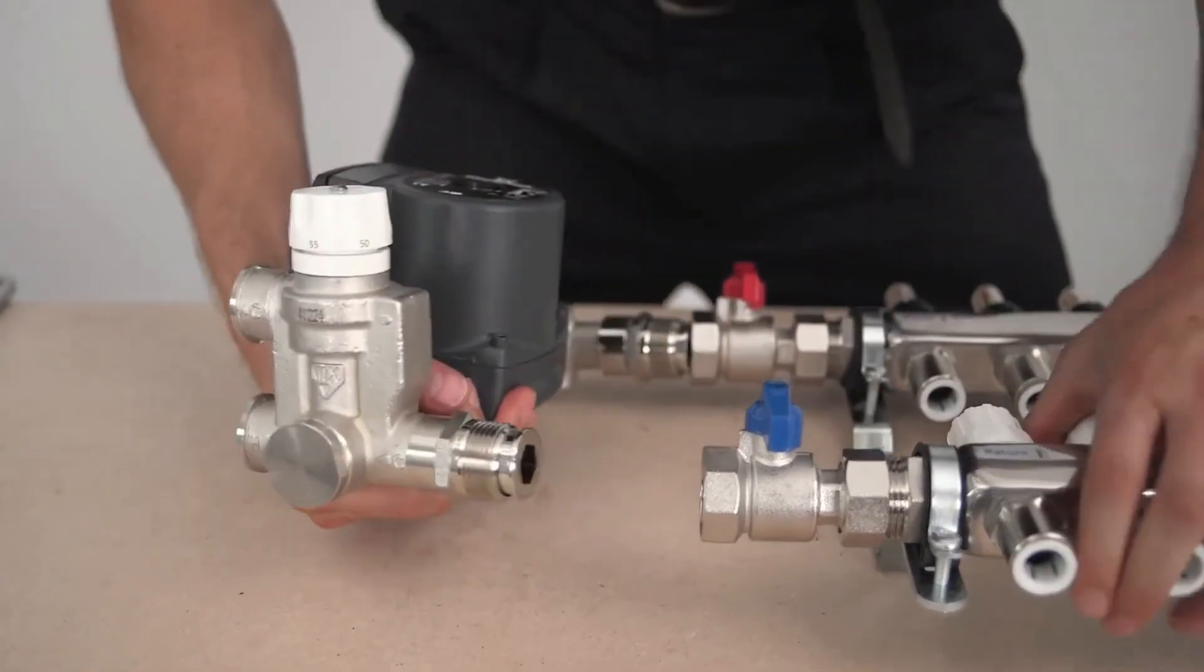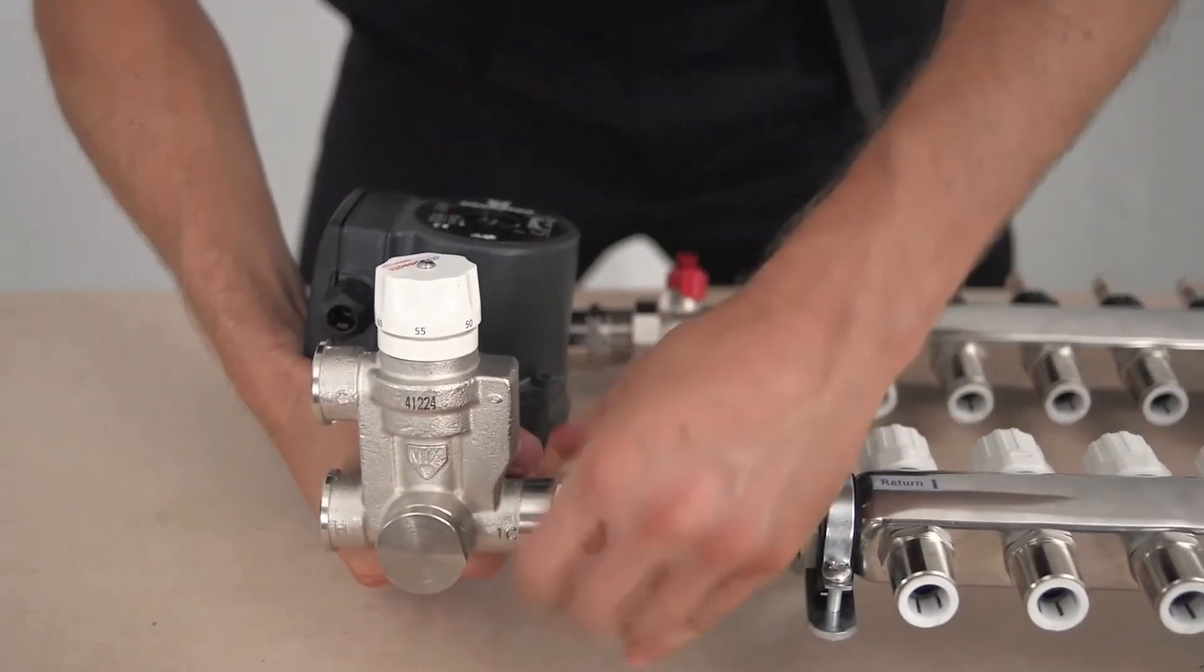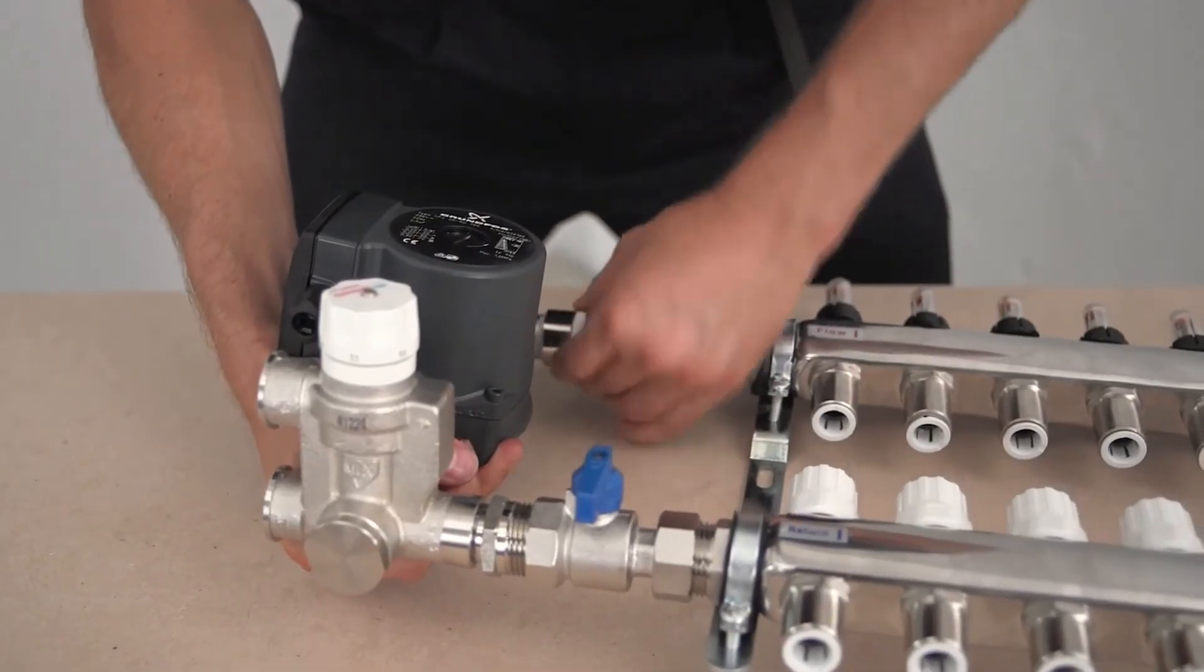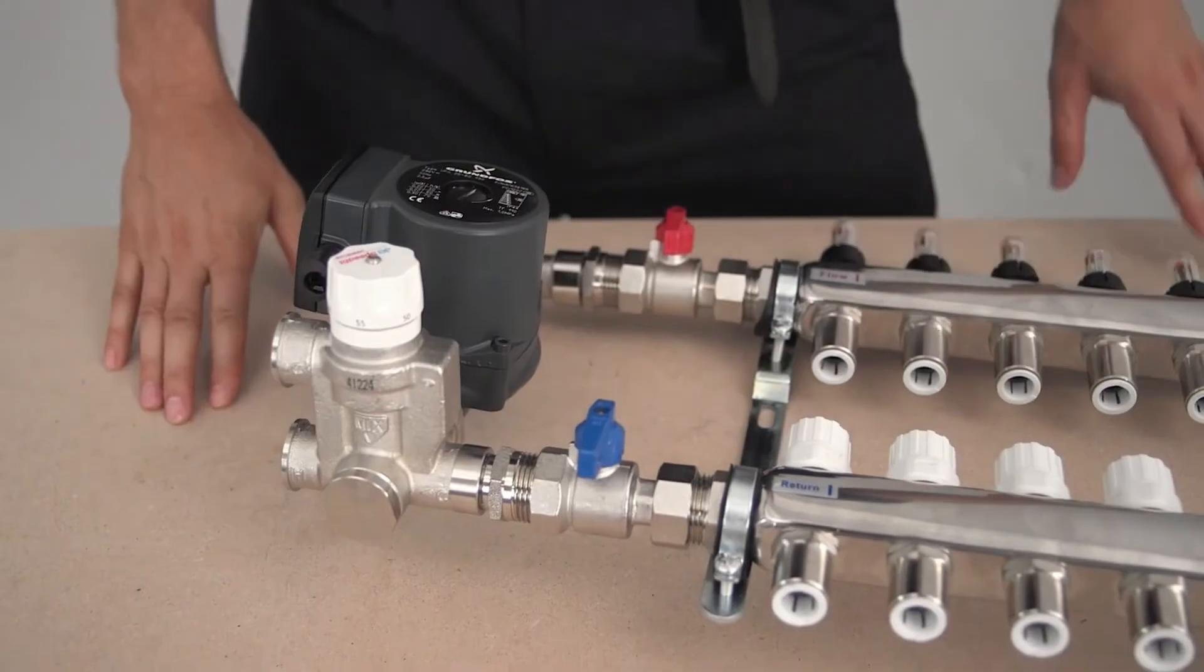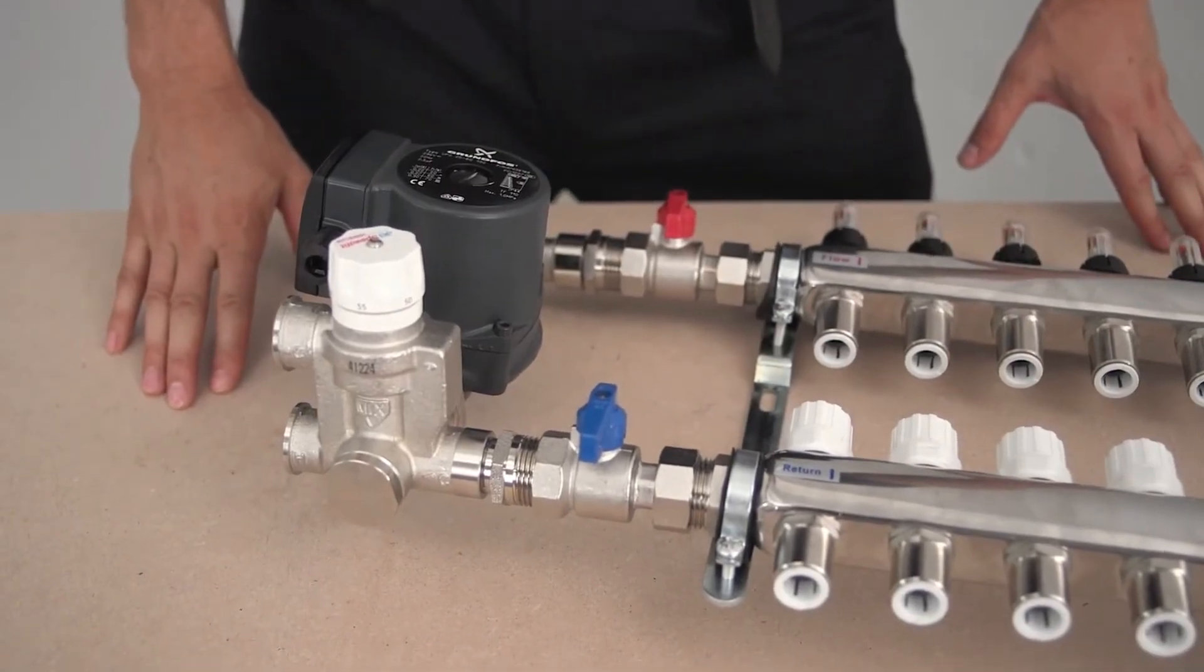The control pack is connected to the isolating valve on the manifold using the washers provided. It performs a number of functions. It blends high temperature water from the boiler with the water in the UFH system to maintain the designated temperature, usually between 40 and 60 degrees depending on the application. It also circulates water around the various UFH circuits. Be aware that this pump will not circulate to and from the boiler.